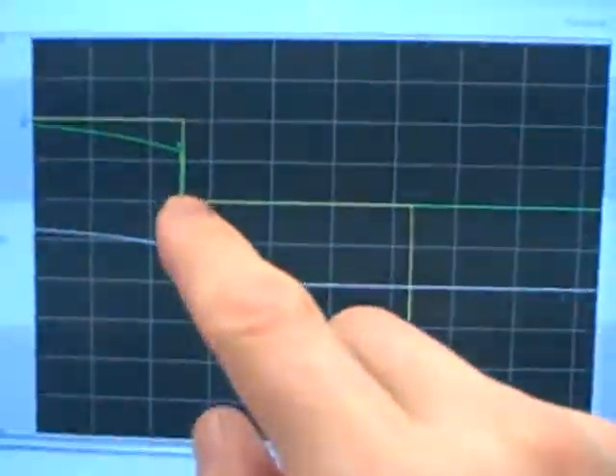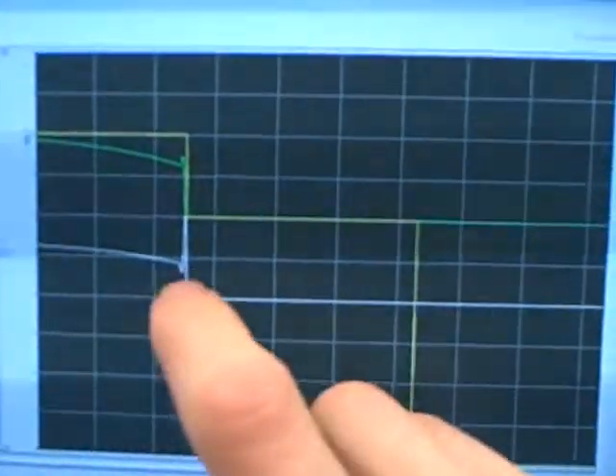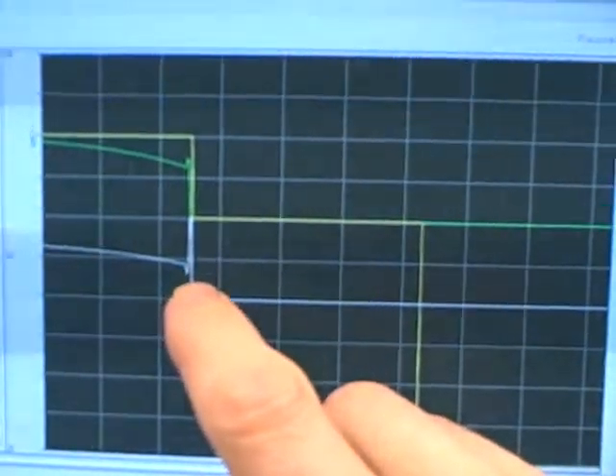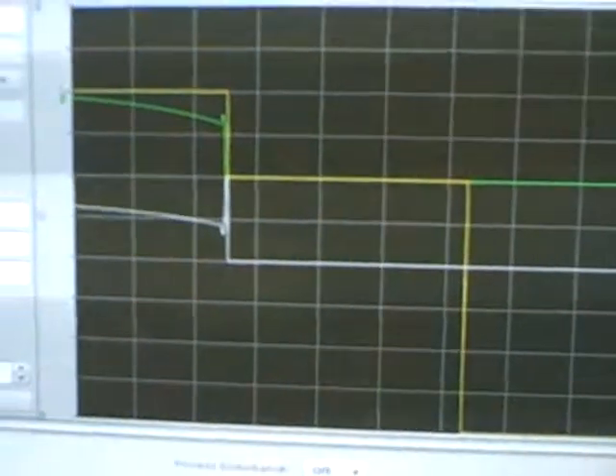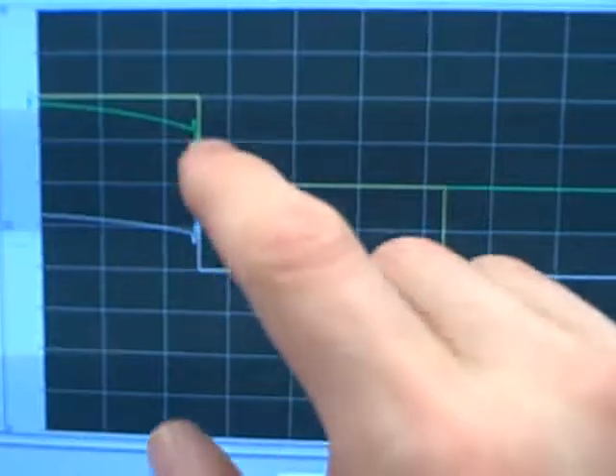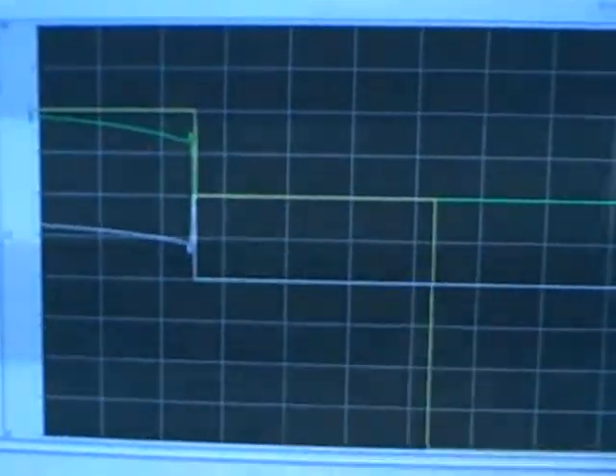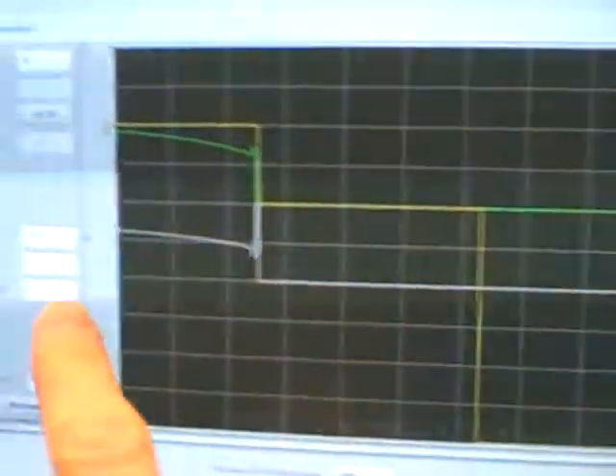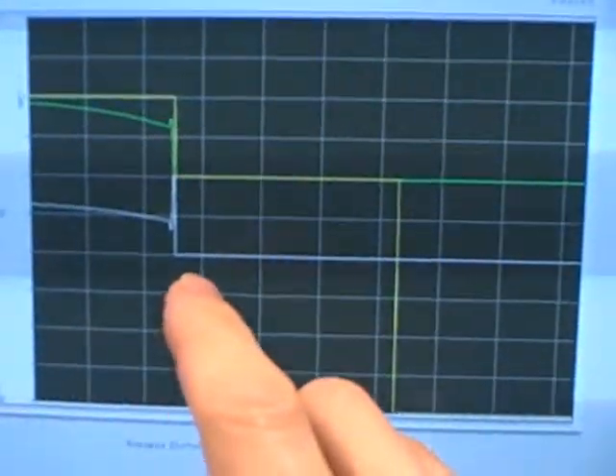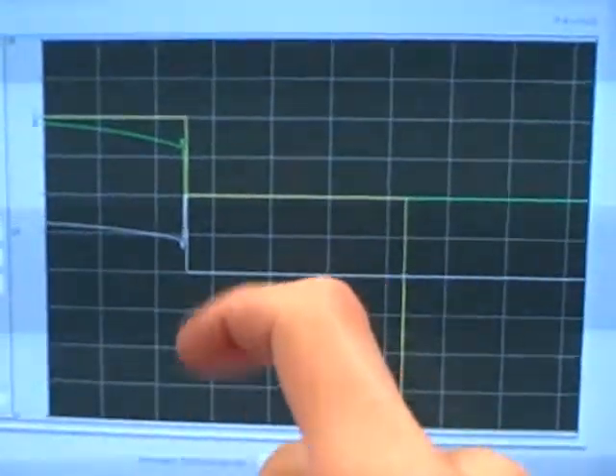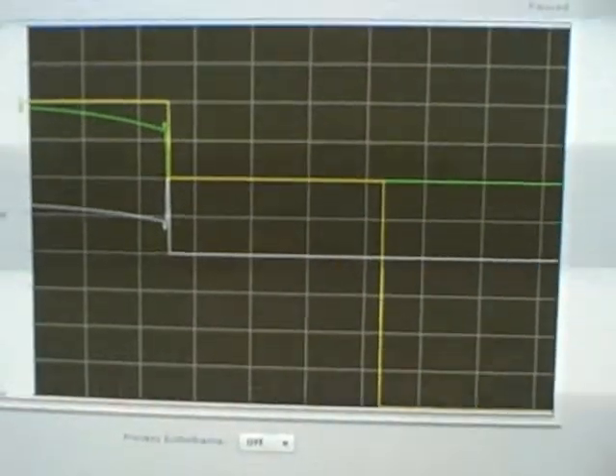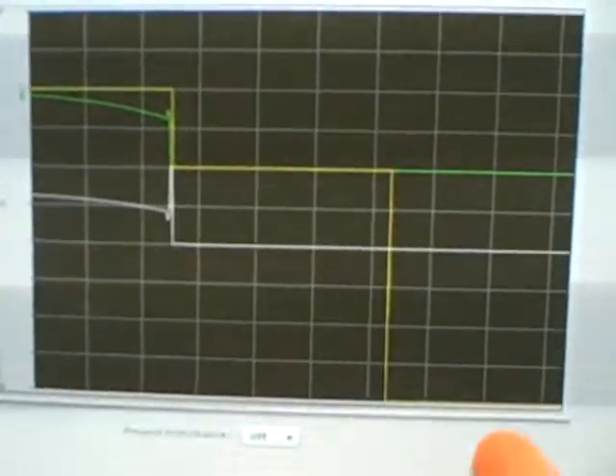Proportional, on the other hand, if it sees the PV value rise, it's going to immediately drop the output. In fact, we see that right here, a spike in the white line, followed by a drop due to proportional action as the PV begins to rise rapidly. So too much gain will cause reversal in valve direction sufficient enough to cause a wobble in the process variable value before it reaches set point. Derivative can also do the same thing. Looking at rates of change, if we had derivative programmed in here, it is possible for it to do porpoising as well. It would see a rise in the process variable, and it would try to correct that immediately by reversing the valve direction. But since in this application we know we have no derivative action, we only have proportional and integral, and we know of those two, the only one that can possibly cause this porpoising is proportional. We know we've got too much of that.